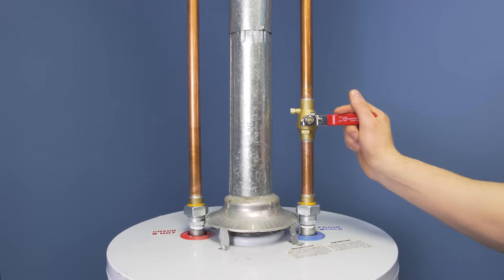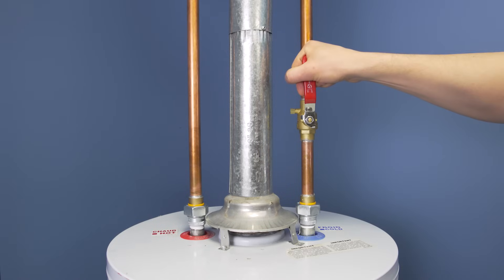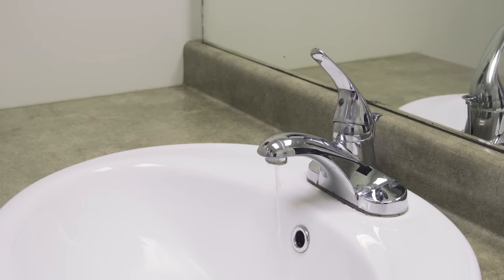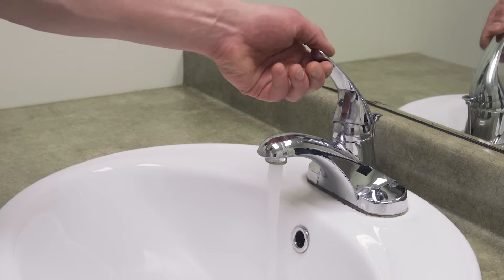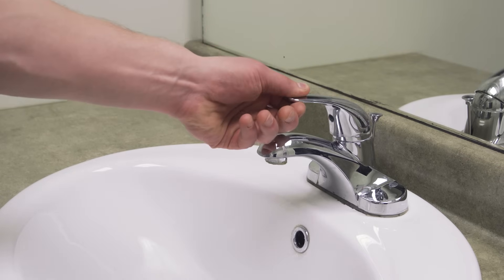Now open the cold water supply to fill the tank. Check the faucet. You should hear the air being pushed out of the system. Close the faucet once you get a smooth stream of water. This will tell you that the tank is full and the air has been removed.